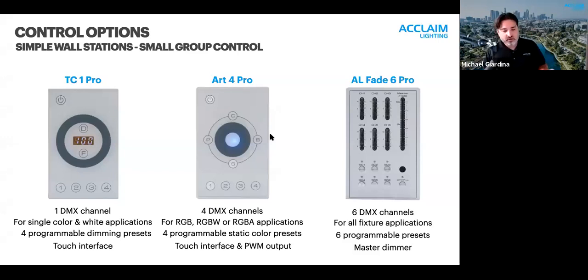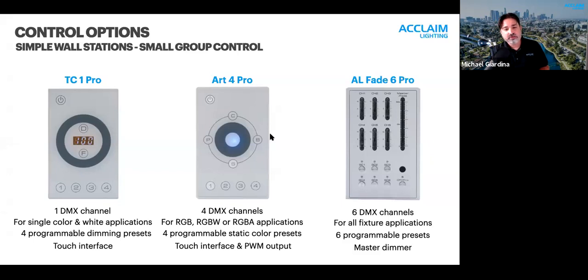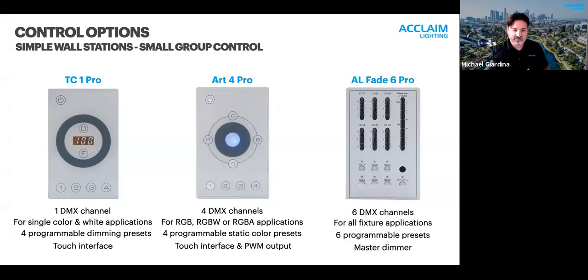We have a couple of questions on DMX cable length. When using a proper DMX cable with RS-485 compatible signal at the right impedance, you can theoretically run DMX cable up to 3,000 feet — we've done that testing reliably in our lab and in the field. The 300-foot number typically thrown around applies to Ethernet/Cat5 or Cat6, not DMX. If you follow the DMX spec, use proper cable, splitting, and isolation, you can get over 3,000 feet of DMX run — that's 32 devices in a single line.